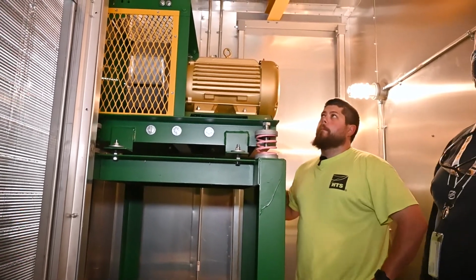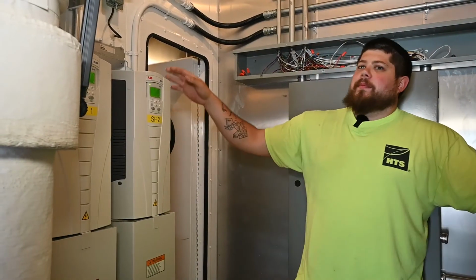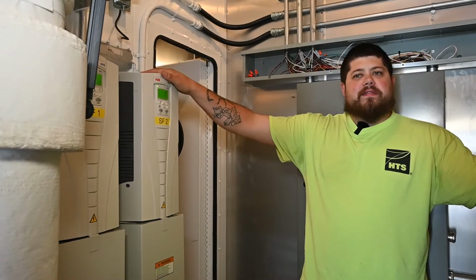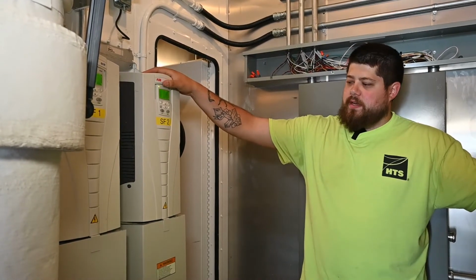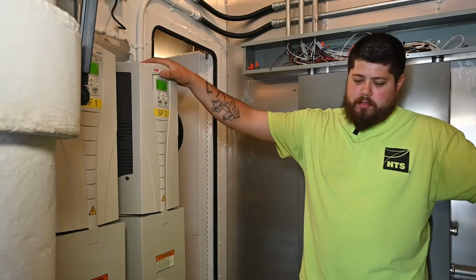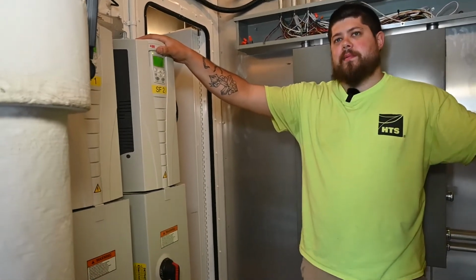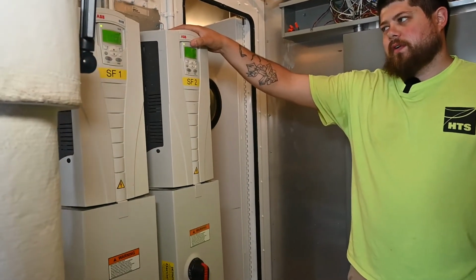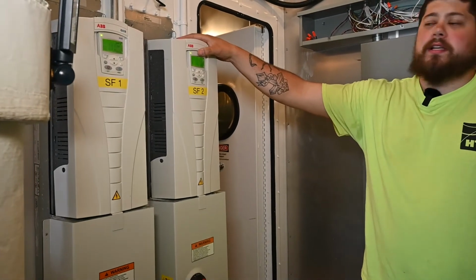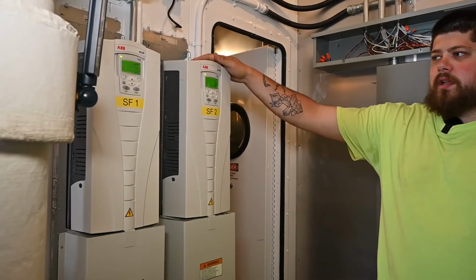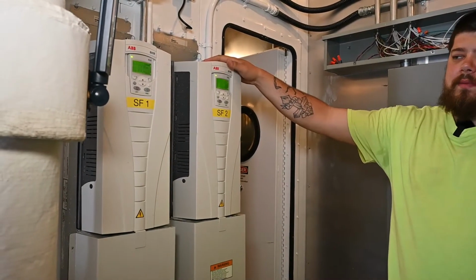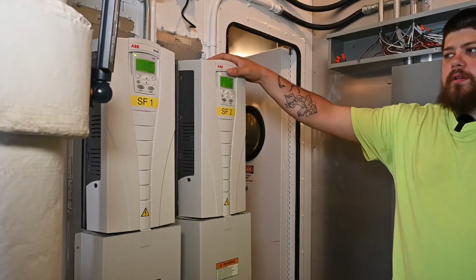Thank you. Yeah. So right here, I want to focus on a couple of things. We have both of our supply fan VFDs right here. There's nothing that needs to get done to them, really. They're good to display if you're doing a maintenance contract and you come up here to look at the unit to make sure that it's not in alarm, or if it is running, that if you shut it down, you shut it down correctly. Both the off buttons here will shut down both drives. Try and make sure you shut them off at the same time so there's no pull on the motors.